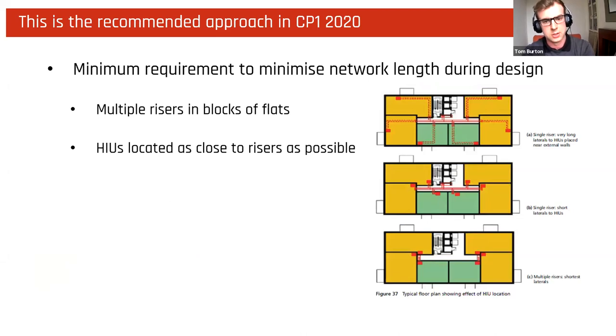So, just to go back to CP1 2020, it's now a minimum requirement to minimize your network length during design. The optimal approach from a network length perspective is to have multiple risers with externally accessible HIUs. That's the way to minimize your communal distribution pipework, so you've got rid of all your laterals, and it's also the best way to minimize your terminal run pipework. You can see that in this diagram taken from the new CP1. It shows the impact of both the HOU location within the flats, and also the impact of lateral pipework compared to multiple riser pipework.